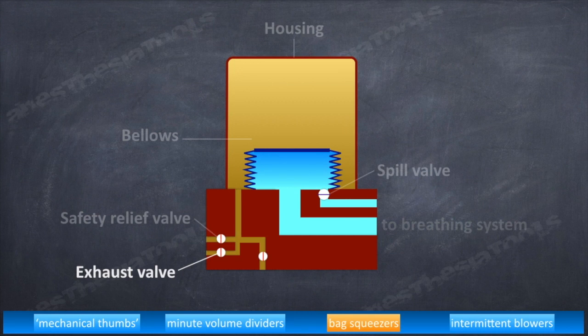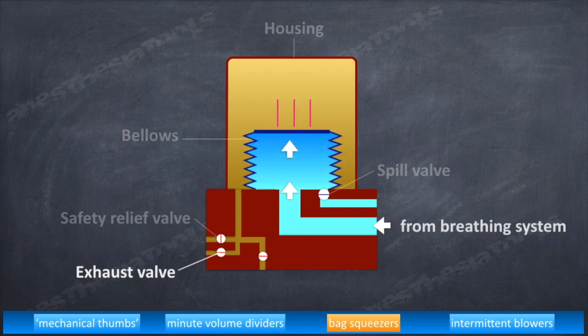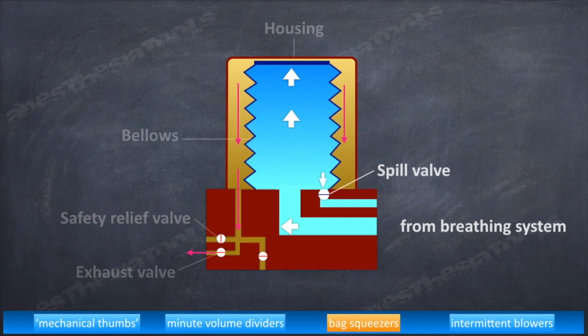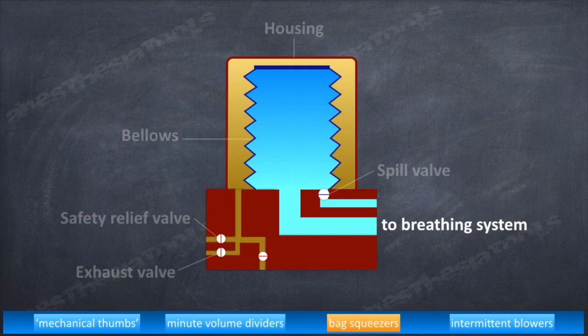Now we cycle into exhalation phase. The inlet valve for the drive gas closes and exhaust valve opens. Gas mixture from the breathing circuit is drawn into the bellows during exhalation as the pressure inside the housing falls. The drive gas escapes through the exhaust valve. Continuous filling of bellows may increase the pressure inside the bellows, causing spill valve to open, and the gas moves out through the spill valve into the scavenging system. The sequence of events repeat during each breath cycle.